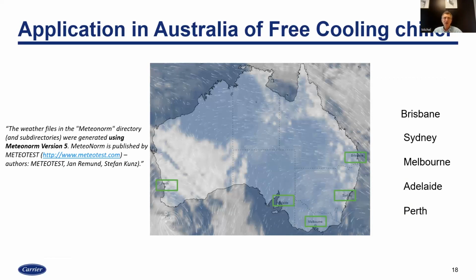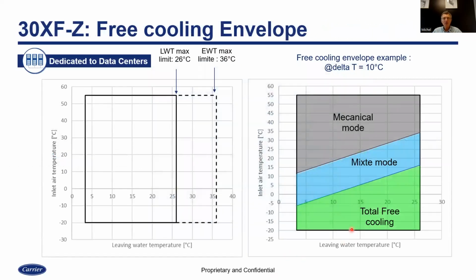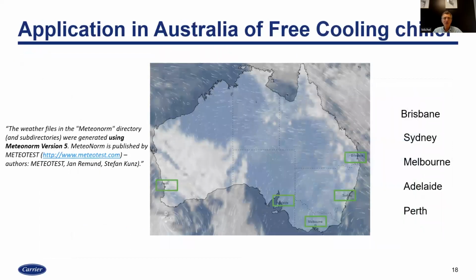Okay. So you cannot say this machine's free cooling has such and such efficiency or will consume such and such amount of energy without saying where it will be installed, what the water temperature will be, or what the load will be. Okay, so those load elements, as I have shown here. Depending on the load and temperature, you may have different results in terms of efficiency.